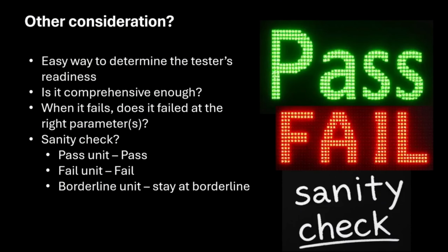So, other considerations when we use a golden unit. It's an easy way to determine the tester readiness. If it's supposed to pass, it passes. If it's supposed to fail, it fails. The question here is, I'm only using one golden unit. Is it comprehensive enough to cover all test conditions? If my unit is only giving a pass result, does it cover the fail portion? These are the questions that you have to ask yourself or your team. When it fails, does it fail at the right parameter? You might have a fail unit that fails at parameter 2, but when you run the test to verify your tester readiness, it might fail at parameter 7. What does that tell you? Is that a good unit? Is it a good check for readiness? These are the things that you have to have in your checklist.